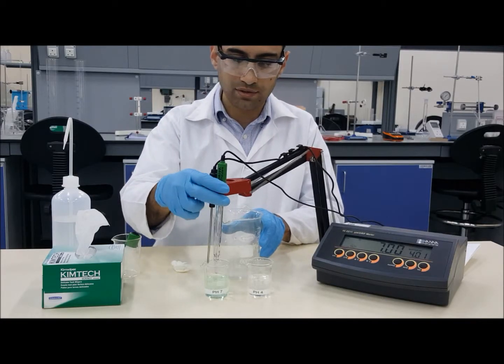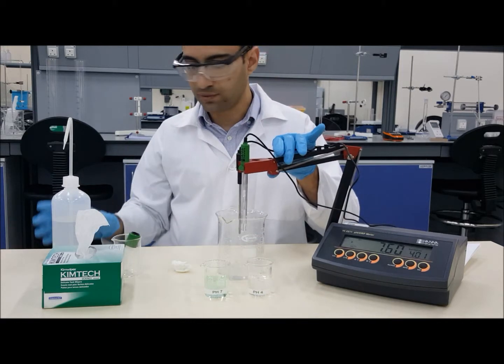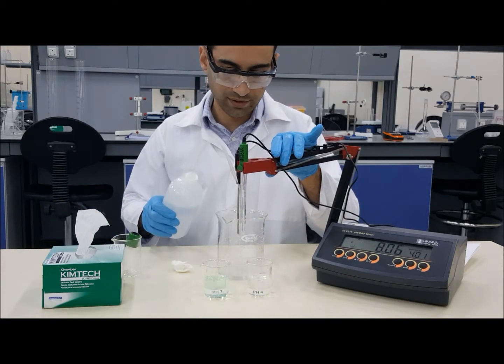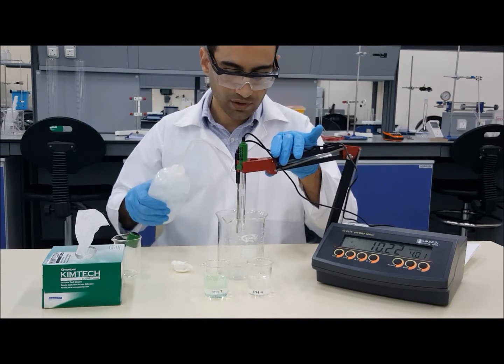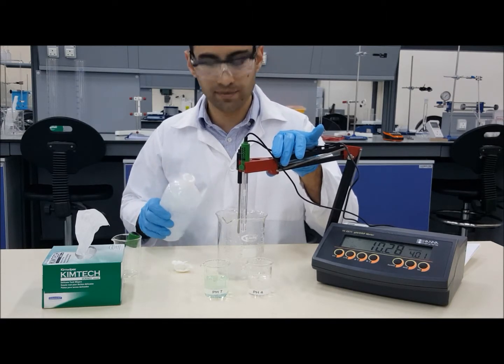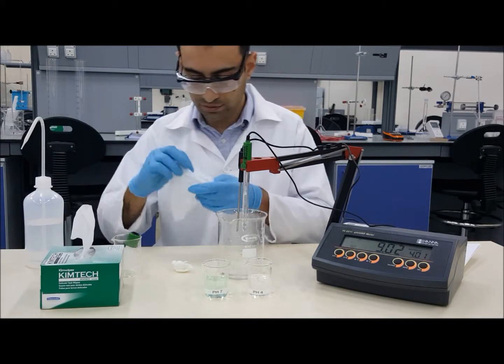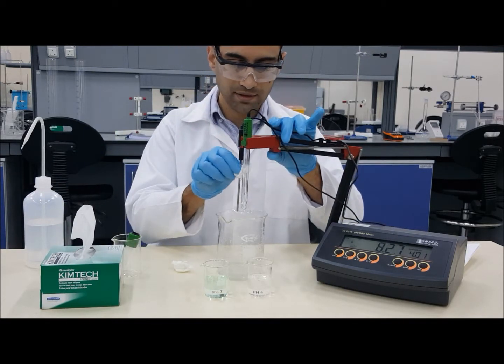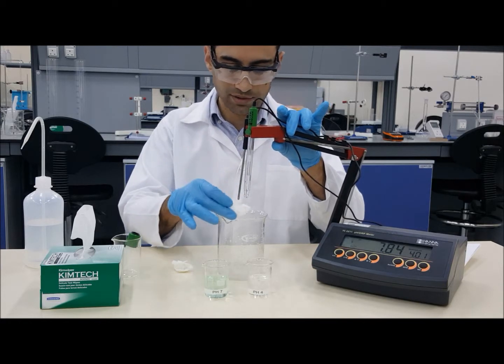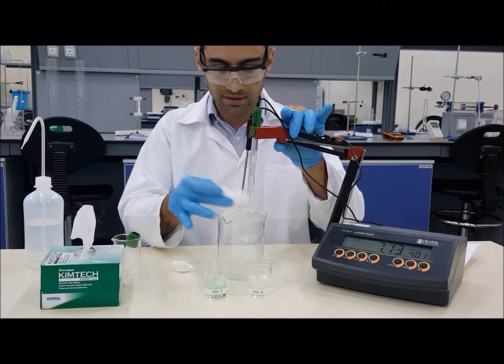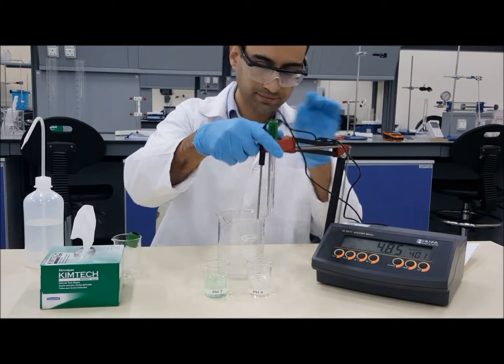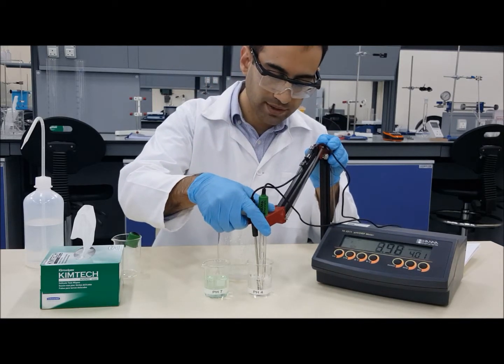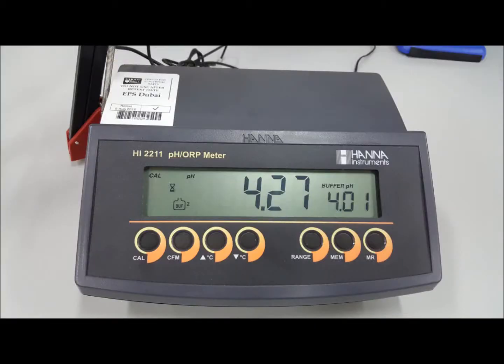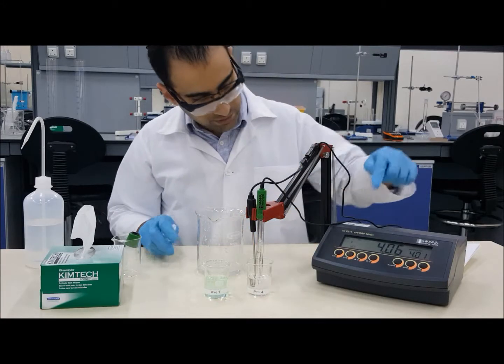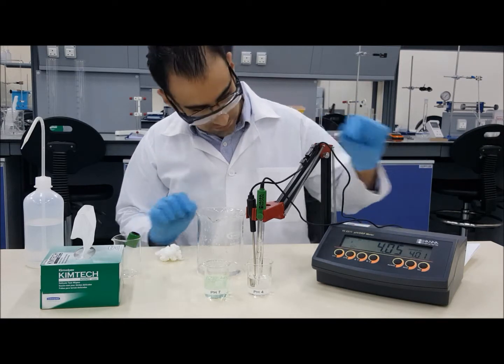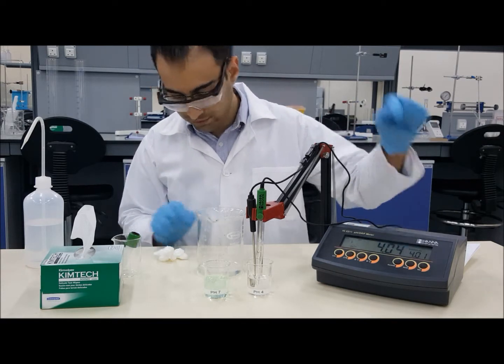So we'll need to get the electrode back up to the large beaker. We'll need to make sure we use some water to rinse the electrode, both of them, temperature and pH. Similarly, we'll use a small tissue to dry the temperature electrode and just remove that extra liquid from the pH. Now we'll get it to the next reading, and we'll wait till we get the ready message in here. Now we can see it's changed to nearby 4.